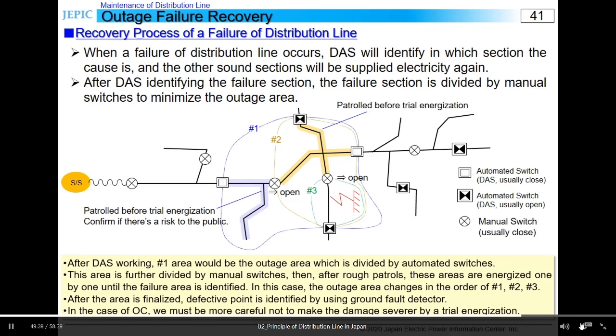In this case, since the cause is in the third area, the trial energization to the light blue line from an automated switch would succeed and the outage area would be the second area. Next, the light orange area is the area to which the trial energization should be done. In the same way as the light blue line, that area would be patrolled roughly, but the trial energization would be done by a manual switch, different from the previous one. The automated switch of the distribution automation system can turn itself off before the CB of the feeder trips, if it detects a ground fault when it turns on. On the other hand, a manual switch doesn't have such a function.